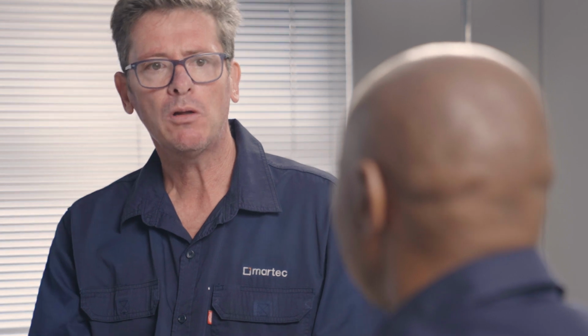So we can tell them what it is. It's a level 1 or a level 5, but we can also tell them where it is. Is it in the switchgear? Is it in the cable? And if it's in the cable, then what would we do? Because a cable could be kilometers long. So once we see that it's in the cable, what we usually recommend is that the client switches off, and then we conduct an offline partial discharge test, VLF, tan delta, and pressure testing on the cable. And we also do PD mapping, which is able to map and tell us the exact location of the PD activity along the cable length.